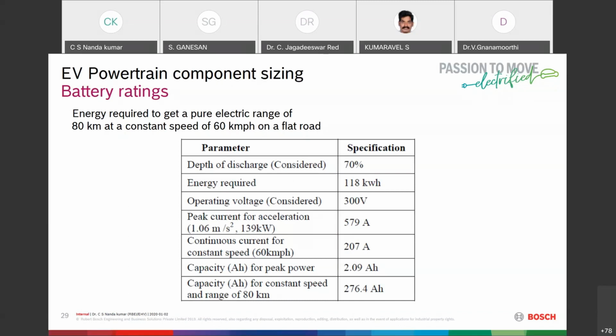This is with a 300 volt operating voltage. So the peak current demand for acceleration is 579 ampere, and continuous current comes to 207 ampere. So the capacity for peak power and the capacity for constant speed will also vary depending on these conditions.